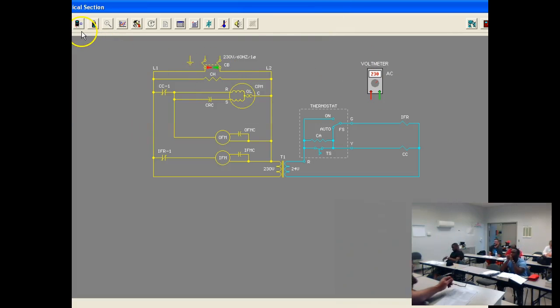So anyway, a voltmeter. I have an amp meter here, right? So there's about 5 or 6 places I can take, 4 places I can take amps. Now I have an ohm meter here, y'all. Y'all hear that? What are my 2 rules of using an ohm meter? So I got to cut my power. Now, when I select ohm meter, let's say I'm going to go my compressor. R to common, 1 ohm. If you look, I know y'all are way back there, but there's a break right here. They have isolated one side of it, right? So there's quite a few places I'm going to click on my ohm meter to check ohms, just like you would in real world.